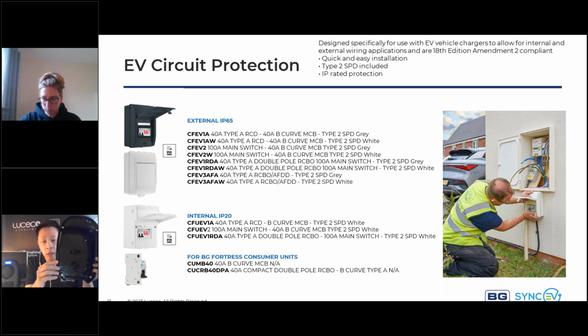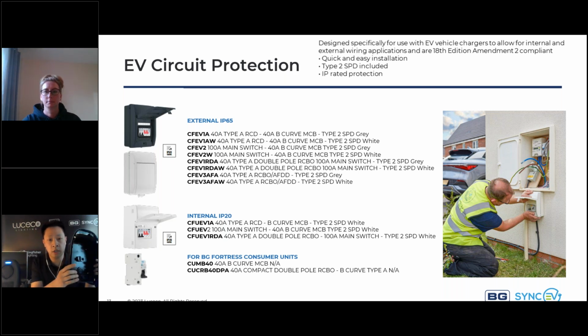Whether it be a 25mm stuffing gland, which is provided in the box, that will go on your right hand side. If it's SWA, that'll go on your left. You've also got, if you can just see there, a rear knockout as well. And in terms of mounting, when you terminate your cables, you'll bring them in from the bottom. Obviously, this is just a little 3-pin cable.